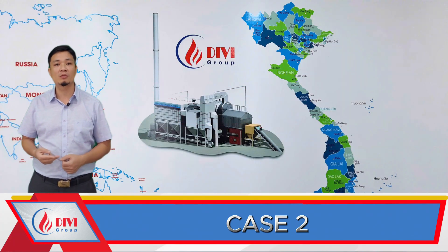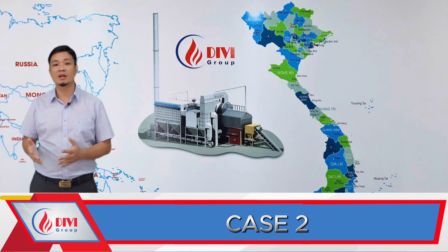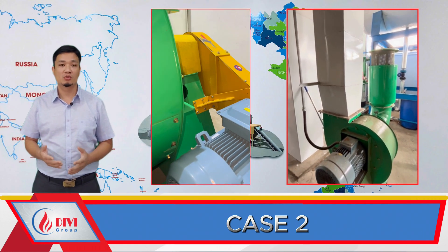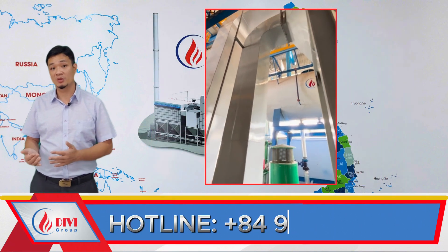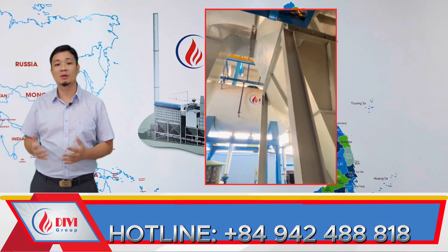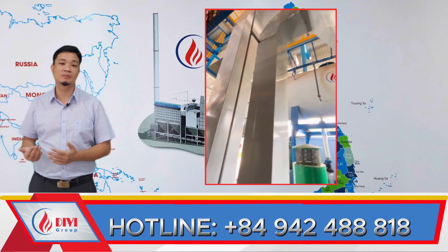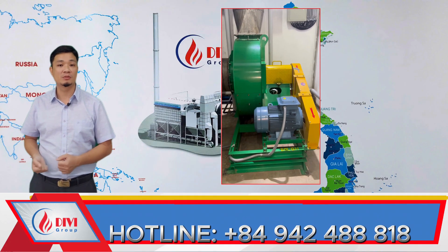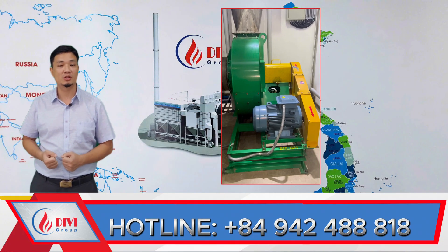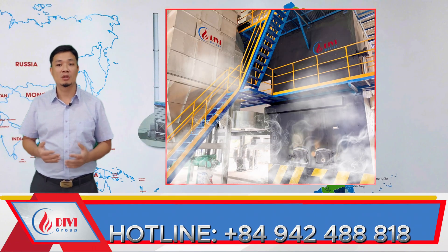Case two: fuel level appears normal, but pressure is still low. Then you should immediately check the primary air fan (forced draft) and the induced draft fan (exhaust fan). If the primary air fan is not working, there won't be enough oxygen in the combustion chamber, which reduces combustion efficiency and steam generation. If the induced draft fan is not working, smoke cannot flow through the heat exchangers, also reducing steam generation and causing smoke to back up and fill the boiler room. The result: steam production decreases and boiler pressure drops.